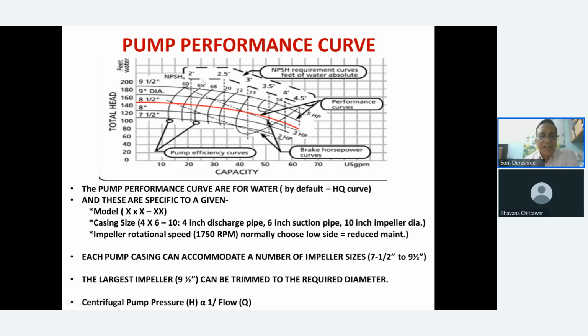Now, these slightly curved lines are basically efficiency curves. You see this efficiency curve moves like this, like a full semicircle. So anything on these points will be at 73. Anything on this point will be at 74. So this is 74, this is 74. If your point is here, your efficiency is 74. If you select a pump at this particular point, then it will be 72 as efficiency. So obviously you want to have the maximum efficiency. Now these are the efficiency points, these half bend lines that you're seeing. Of course, if you take the curve, all efficiency curves will go like that.